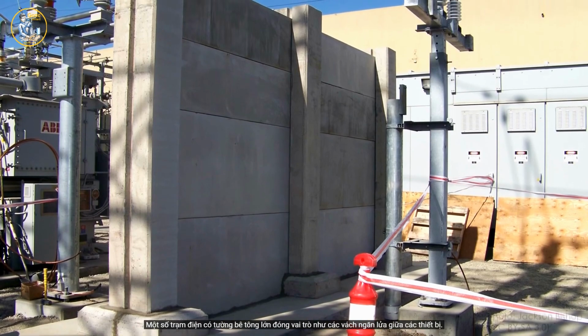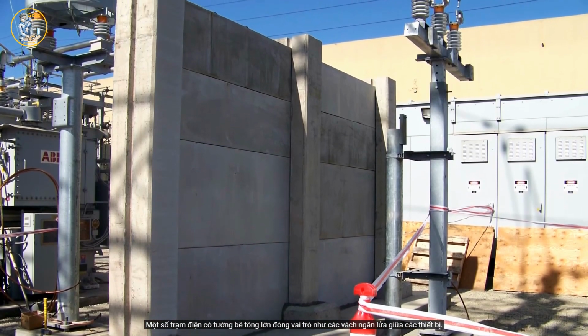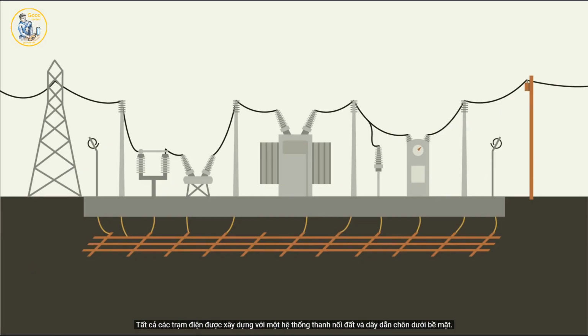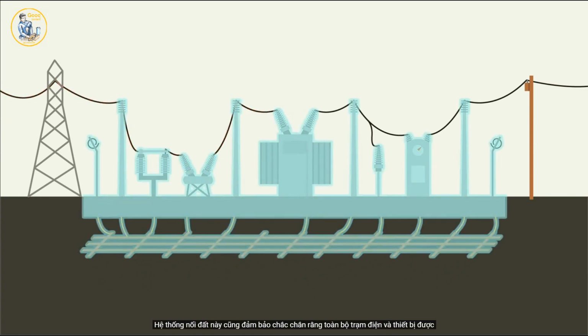Some substations have large concrete walls to serve as fire barriers between equipment. All substations are built with a grid of grounding rods and conductors buried below the surface. In the event of a fault, the substation needs to be able to sink lots of current into the ground to trip the breakers as quickly as possible. The grounded grid also makes sure that the entire substation and all its equipment are kept at the same voltage level, called an equipotential, so that touching any piece of equipment doesn't create a flow of electricity through a person.